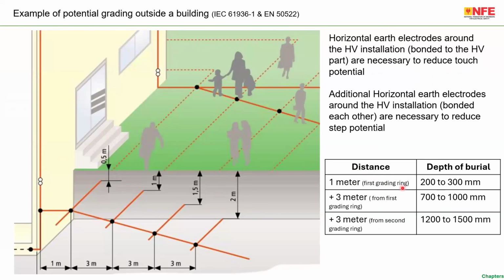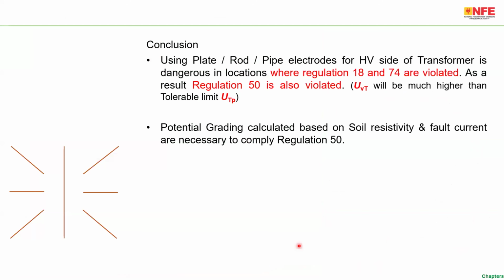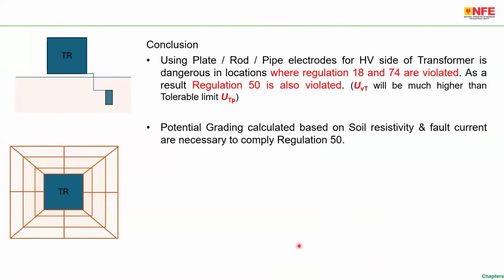say 1 meter away from your transformer, 200 to 300 millimeter deep, you should make a ring, the ring number 1. The second ring is again 3 meters from the first ring, 700 to 1000 millimeters below. The third ring, again 3 meters away from the second ring, 1200 to 1500 mm below. So basically, by this method, we are supposed to calculate the grading rings, and we are supposed to install grading rings all around the transformer in order to protect people from shock voltages.